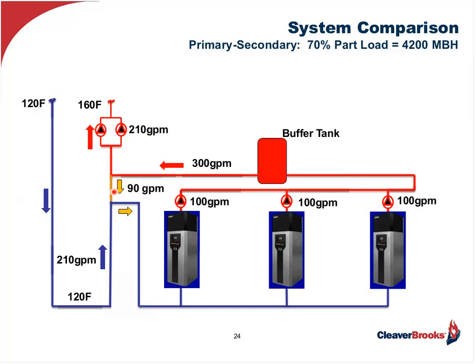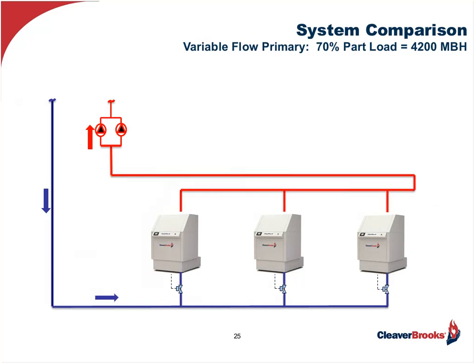That's going to give us 130 at the boilers, not the 120 the system is designed at. The firing rate will be 75%. Again, let's contrast that with the variable primary. The system isn't going to change. That's going to be 160, 120, 210 GPM. But we're going to run all 3 boilers just like on the other system. They're going to see reduced flow, only 70 GPM.